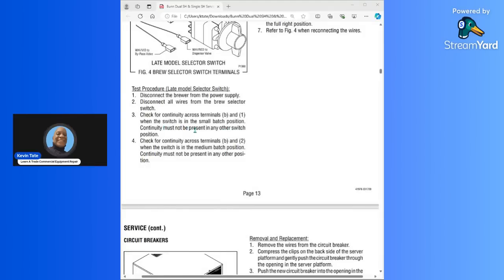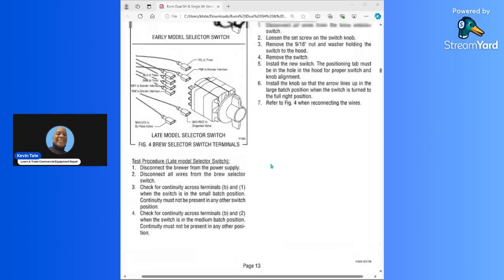When the selector switch is in the small batch position, continuity must not be present in any other switch position. Check for continuity across terminals B and 2. When the selector switch is in medium batch position, continuity must not be present in any other position. So this is why they're checking these terminals here.